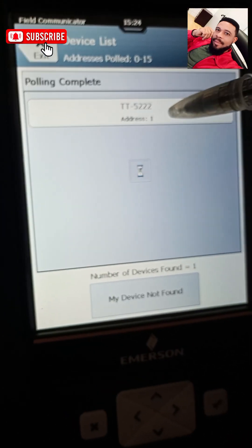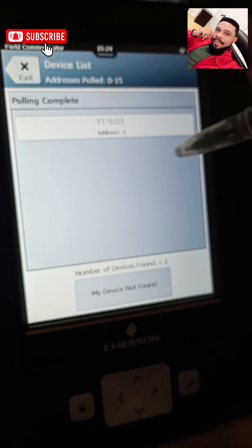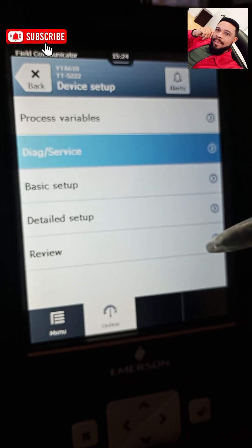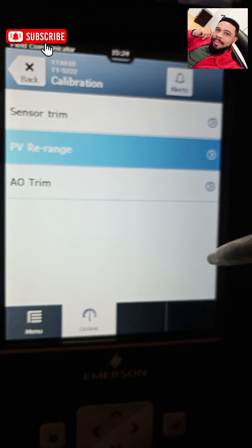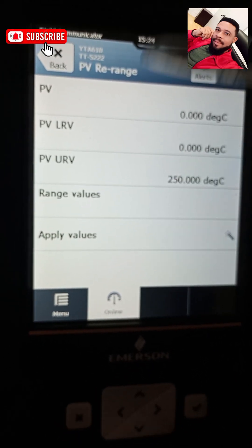This is the tag number of my HART communicator. From device setup go to Diag/Service, then calibration, and then re-range. You have your process variable, process variable lower range value, process variable upper range value, and your range value. Thank you — hope you enjoyed this video. Don't forget to like this video, subscribe for more interesting videos on instrumentation and control, and thank you for watching.